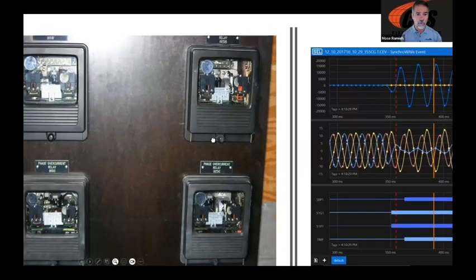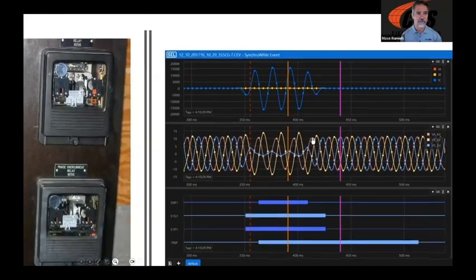Well, when we upgrade our relays, we get all of this tremendous information, right? We can see here's the fault that occurred. We can, you know, once again, we get our information about how long it took our breaker to trip, things of that nature. So it's really important to do that.